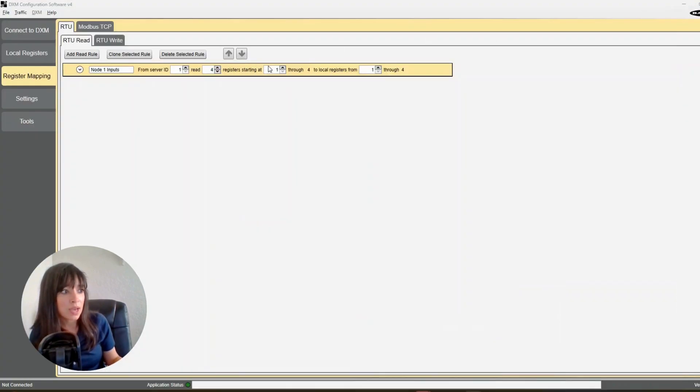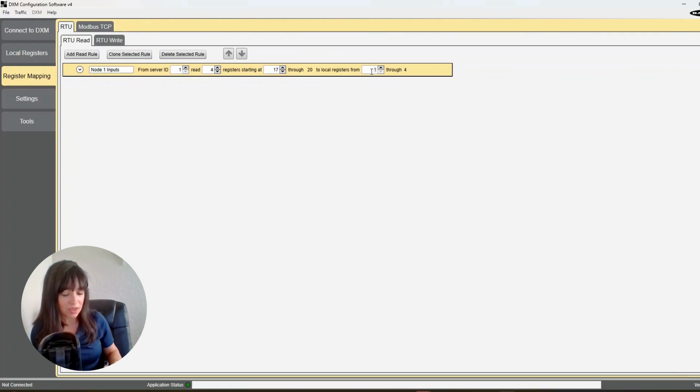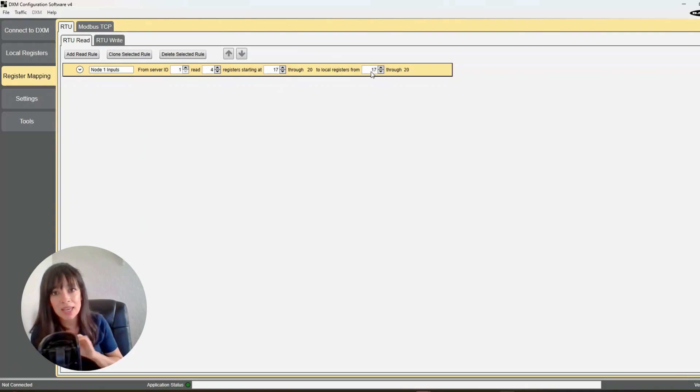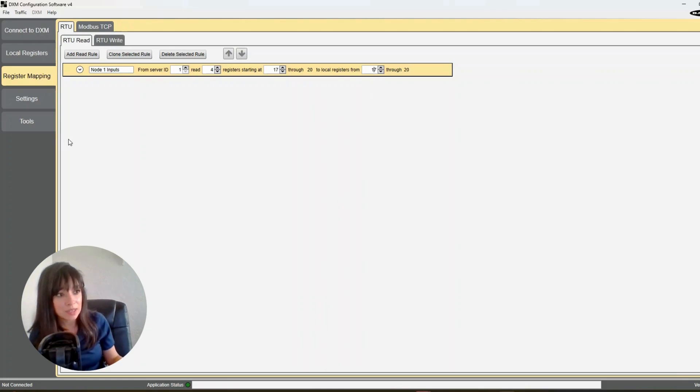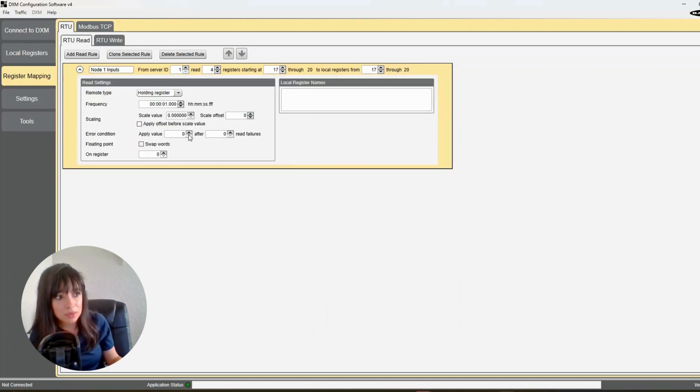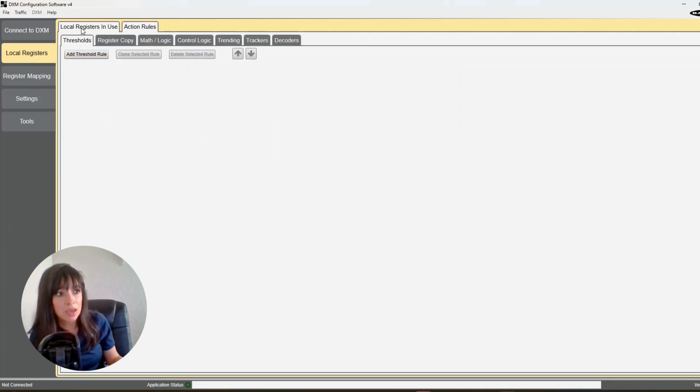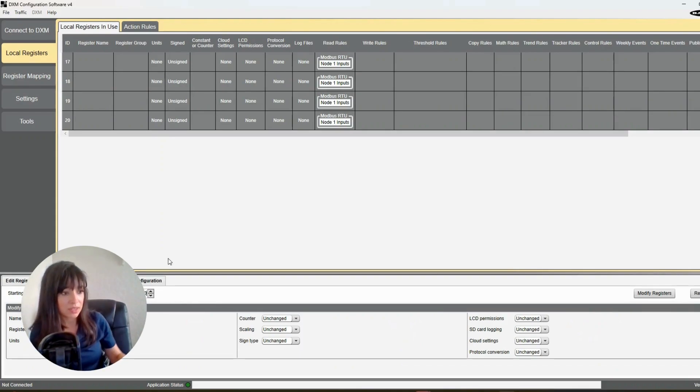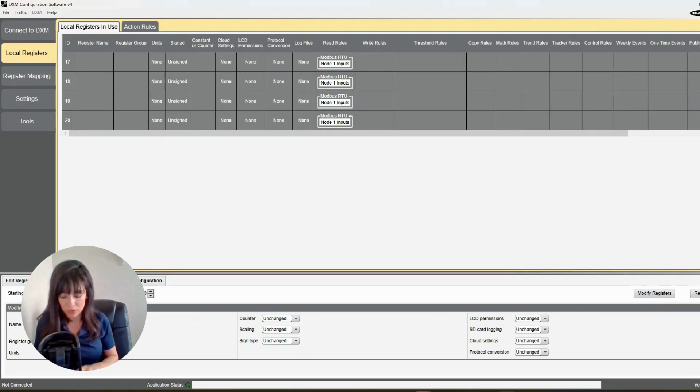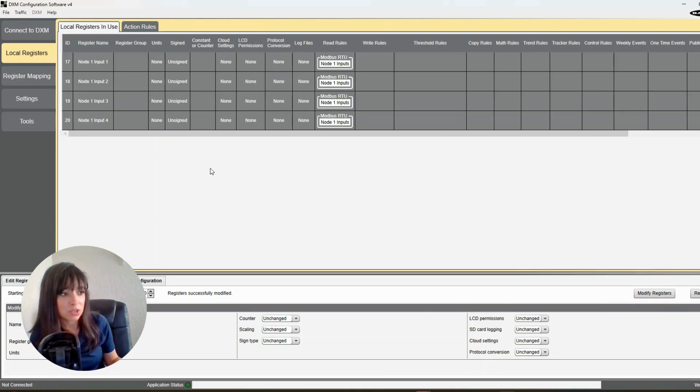So I'm going to type in here 17, and now I'm going to copy that holding register onto my DXM local register. This is where I can pick a value here and I'm going to keep it at the same numbering convention that is used. It's the easiest for me to remember, so I'm going to keep it at 17. The next thing I like to do is leave all of that alone and go to my local registers. I'm going to name all of those registers, so I'm going to start at 17 and at 20, give this a name: node 1 input, space, checkbox, increment starting at 1. Click modify registers and I've got all of those labeled now so I don't get lost and crazy.